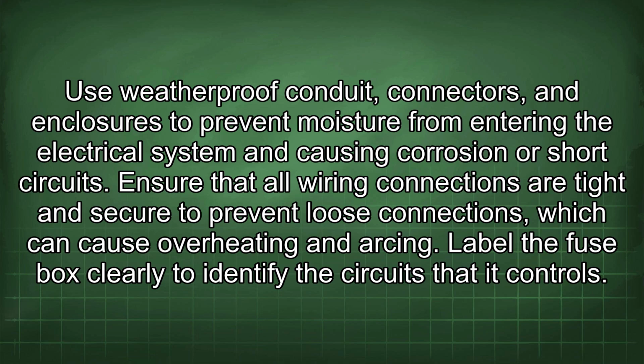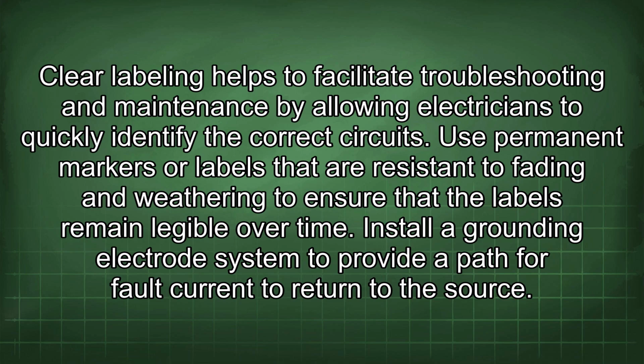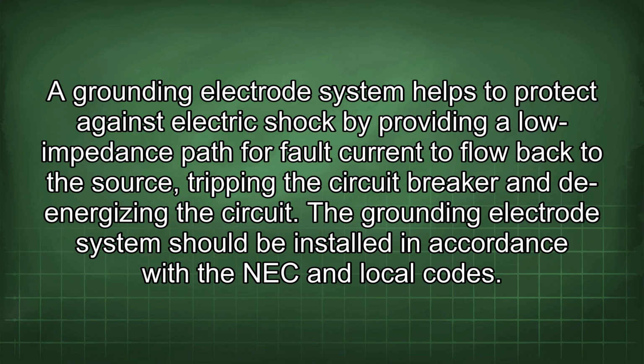Label the fuse box clearly to identify the circuits that it controls. Clear labeling helps to facilitate troubleshooting and maintenance by allowing electricians to quickly identify the correct circuits. Use permanent markers or labels that are resistant to fading and weathering to ensure that the labels remain legible over time. Install a grounding electrode system to provide a path for fault current to return to the source. A grounding electrode system helps to protect against electric shock by providing a low impedance path for fault current to flow back to the source, tripping the circuit breaker and de-energizing the circuit. The grounding electrode system should be installed in accordance with the NEC and local codes.